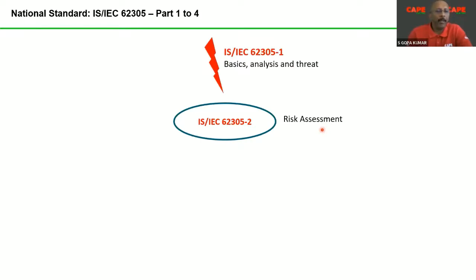Say for example, a small building, a normal residential building, probably lightning protection may not be required. Whereas for a large building, a high-rise building, lightning protection may be required, or is required mandatorily. So that decision can be taken by making a small risk assessment. Then, if your building requires lightning protection, it is classified into 4 levels, level 1 to 4. The second question is, your building requires lightning protection, and what is the minimum level of lightning protection required? It is not to find out what maximum protection is required, but what minimum. That means whatever money you are spending for installing lightning protection, it has to be economical and it has to be useful. That is explained in part 2, risk assessment.